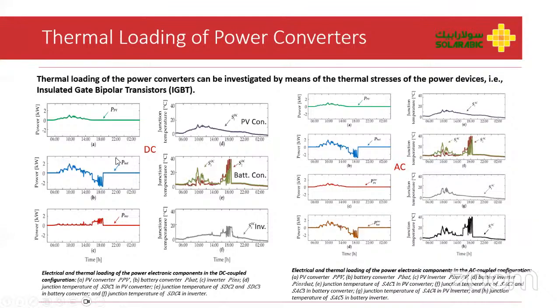Okay, so what we see here, if we look at the thermal loading of the electrical devices in the PV converter, between both configurations it is the same. Similarly, for the battery, it is the same. But when it comes to the inverter, we see a difference in the thermal loading of the electronic devices in DC and AC. Similarly, when we study the junction temperatures between the inverter and the converters, we see differences. For example, here on graph F for the DC coupled configuration and graph G for the AC coupled configuration, you see a difference in the thermal loading stress on the electrical devices. And yet again, in an AC coupled configuration, since we have another conversion unit for the battery conversion, that is also subject to thermal loading stress on the electrical devices.